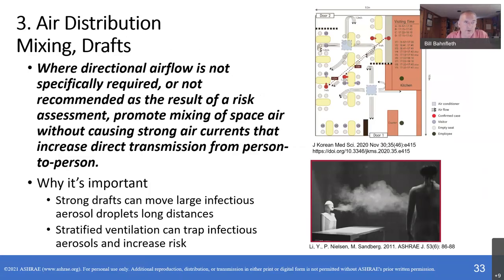So moving on to air distribution, we are giving a soft endorsement for mixing as a good way to reduce risk, because distributing infectious aerosol as uniformly as possible in a space tends to lower the concentration to which anyone is exposed. And also this recommendation discourages the use of air distribution that creates strong drafts.